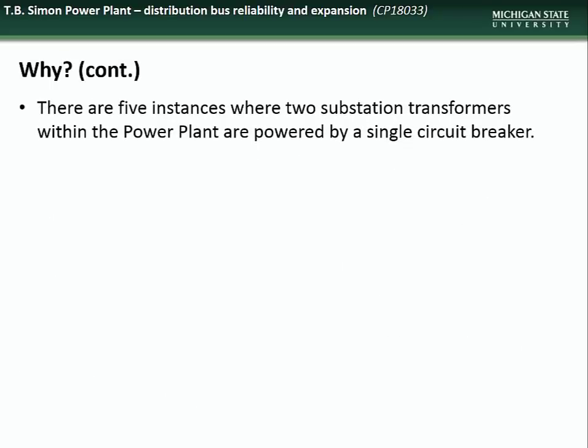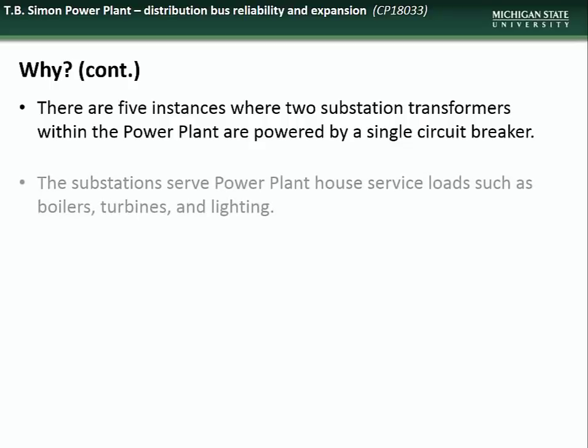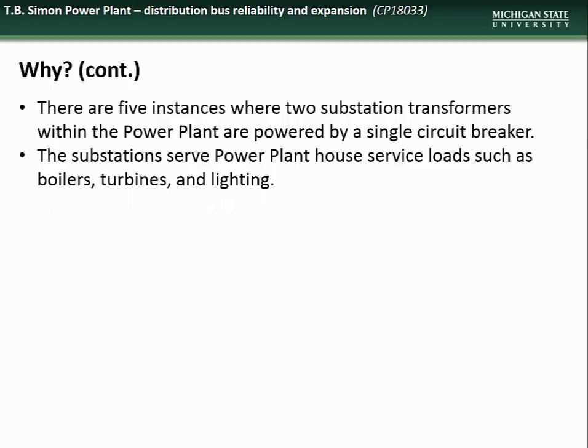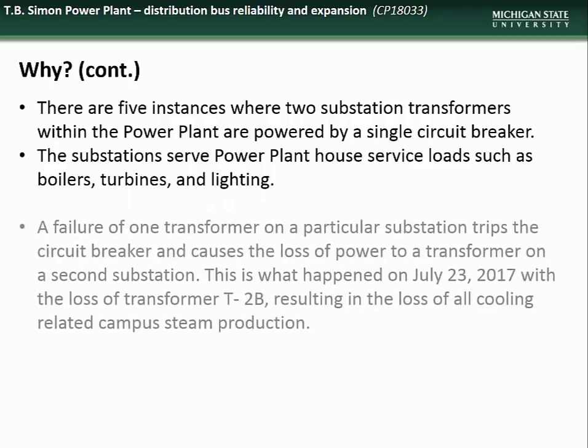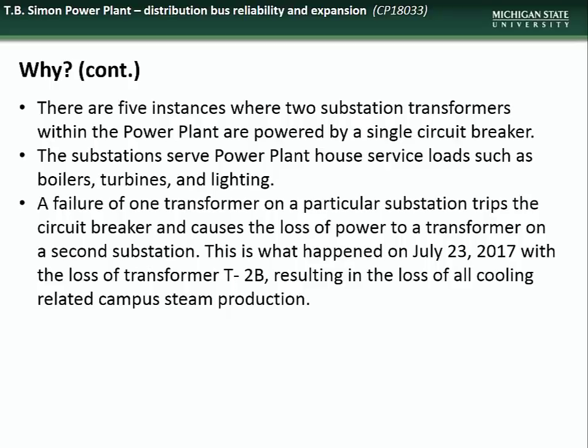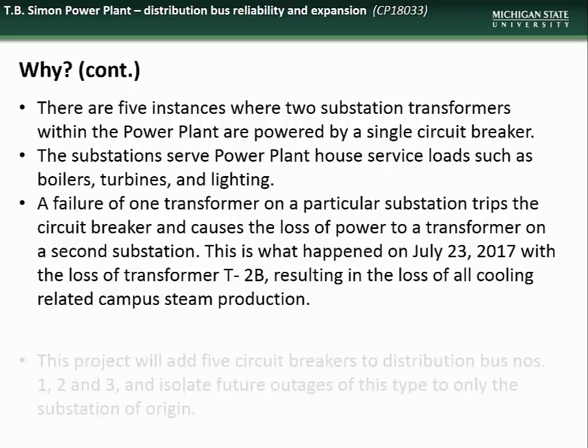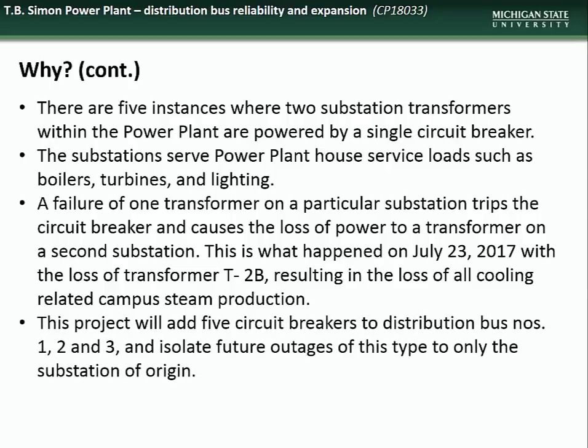Additionally, there are 5 instances where a single circuit breaker powers 2 different substation transformers. These substations serve the power plant's boilers, turbines, and lighting. Unfortunately, the failure of one transformer causes the breaker to trip, which causes a loss of power not only to that transformer, but also to the second transformer on the same breaker, which can have significant consequences to steam and power production. This project will add 5 additional circuit breakers, which will allow for the isolation of these transformers to a single breaker, thus preventing this cascading of power loss.